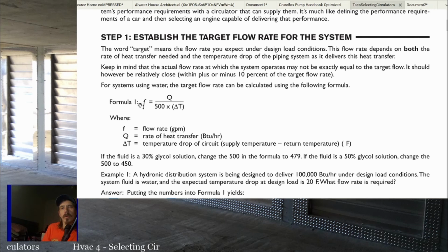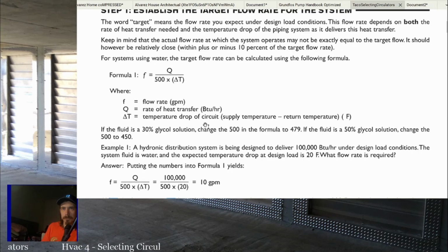So F is our flow rate, and that's going to equal Q, the rate of heat transfer, so that's your BTUs per hour in the system, right? Divided by 500 times our delta T. All right. If the fluid is 30% glycol, change the 500 in the formula to 479. If the fluid is 50% glycol, change the 500 to 450.